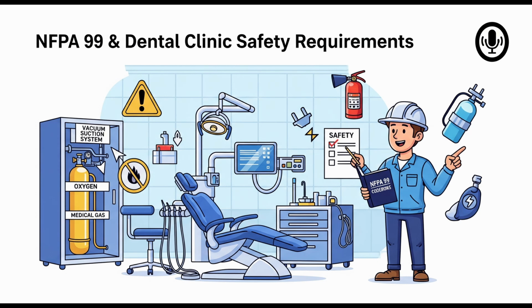You absolutely must keep fuels and oxidizers separated. That seems fundamental. Any other location rules? Yes, a couple more. Indoor storage rooms shouldn't open directly into areas where medical gas is being used, like treatment rooms, or other areas where oxidizers are stored. And if you have an outdoor storage enclosure right next to the building, it needs to be located more than 3.05 meters, 10 feet away from any windows or doors in that adjacent building wall. These are buffer zones for safety.